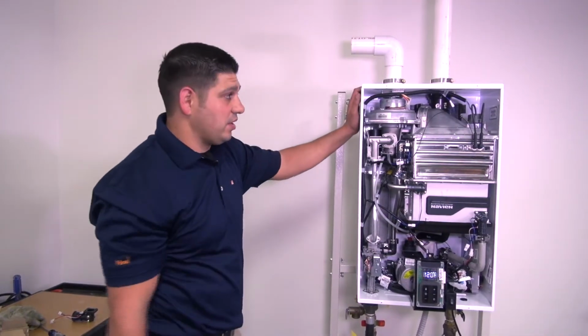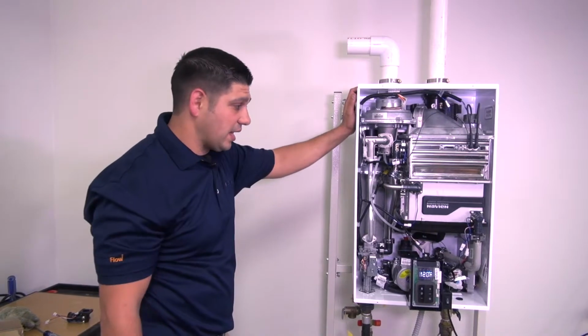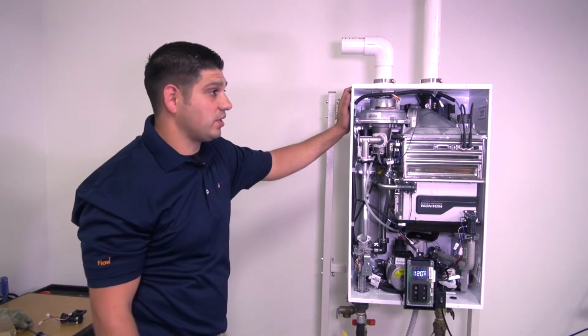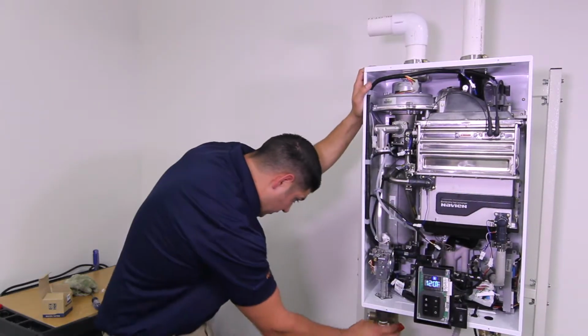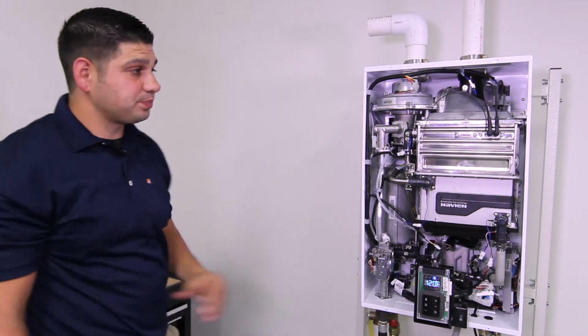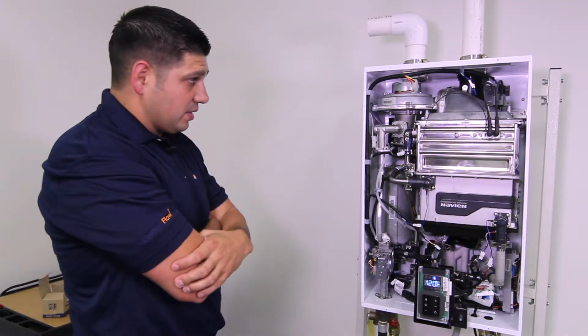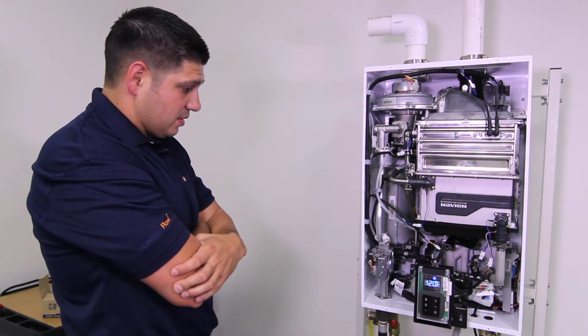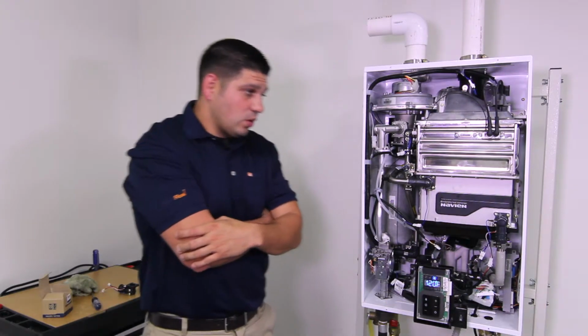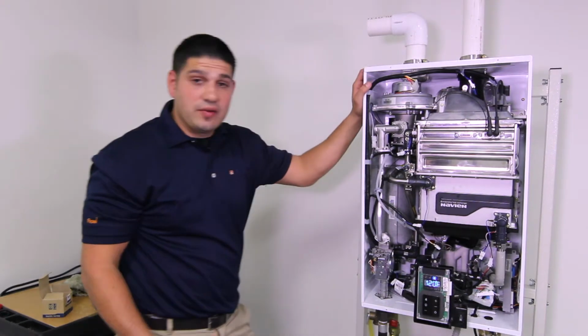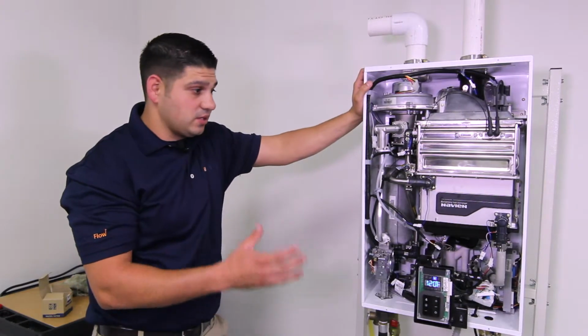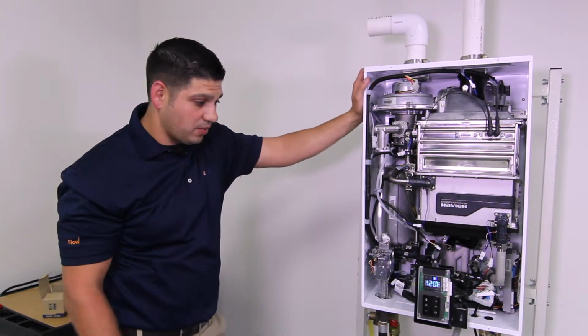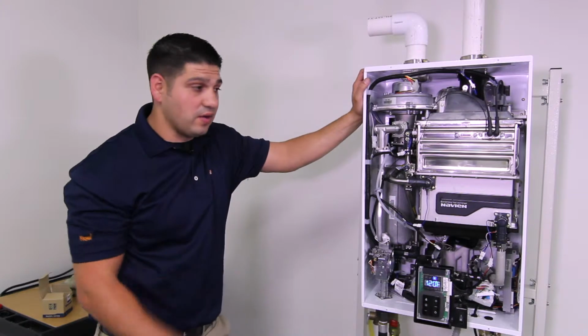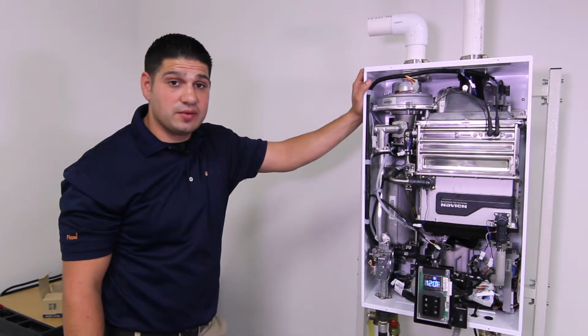We did just turn on the vent hood. We are doing this in the lab, so that's the noise you're hearing, our vent hood kicking on. Open up all the valves, make sure they're 100% open. So what I'm doing here, with the cover off, I want to just physically inspect to make sure the unit is operating at 100% operation. Make sure there's no leaks, and my entire flow sensor replacement went out fine.